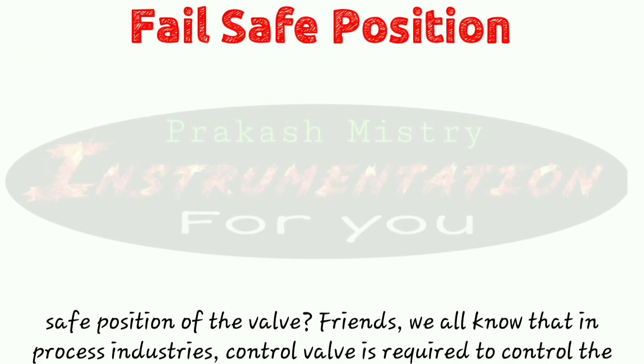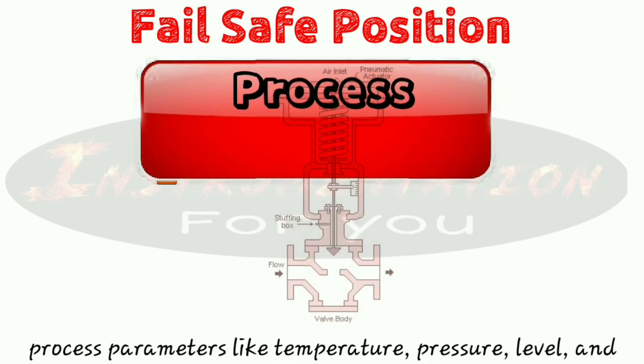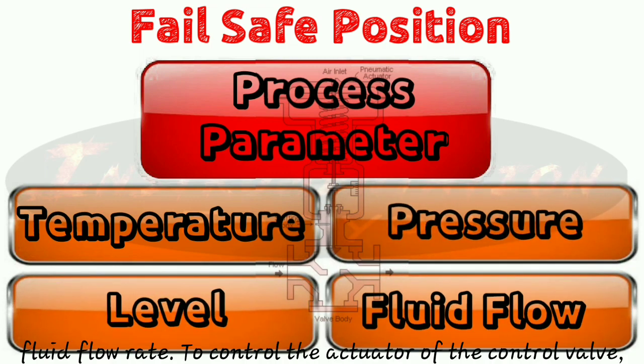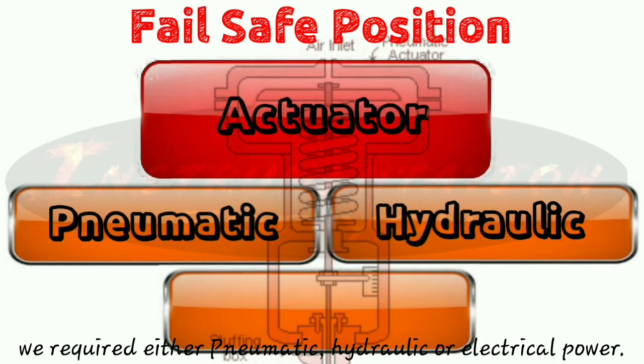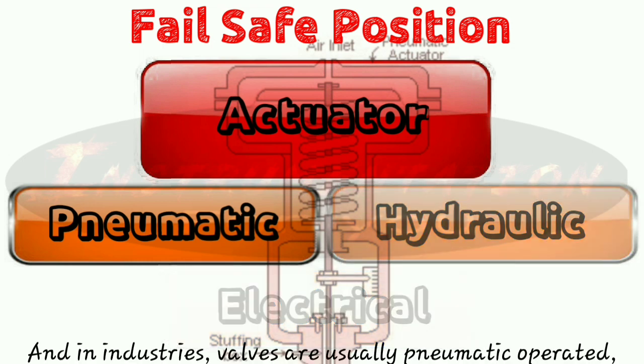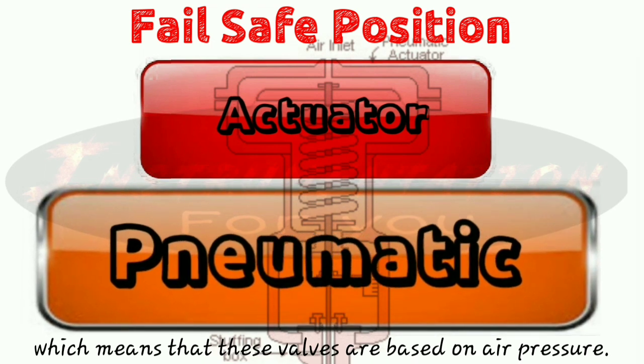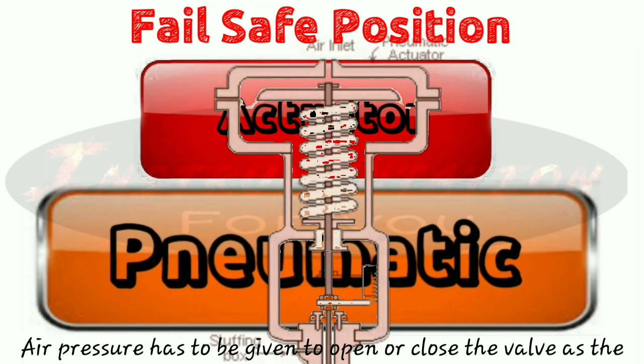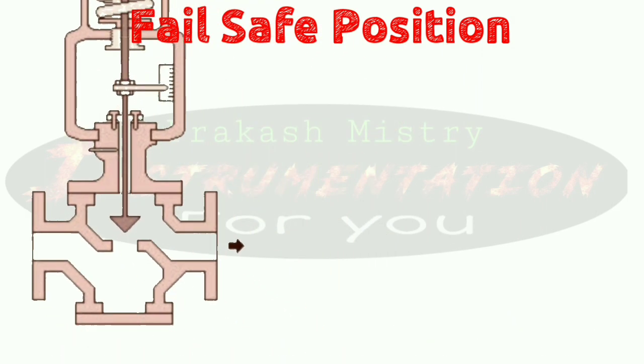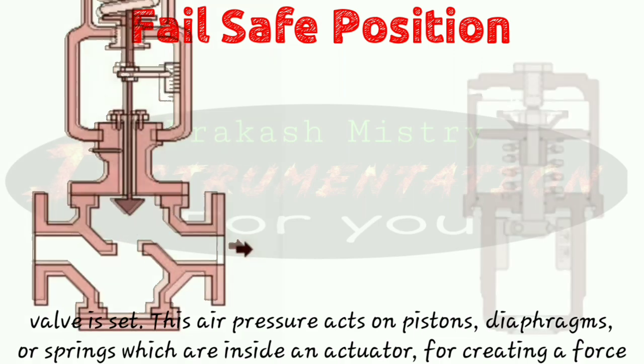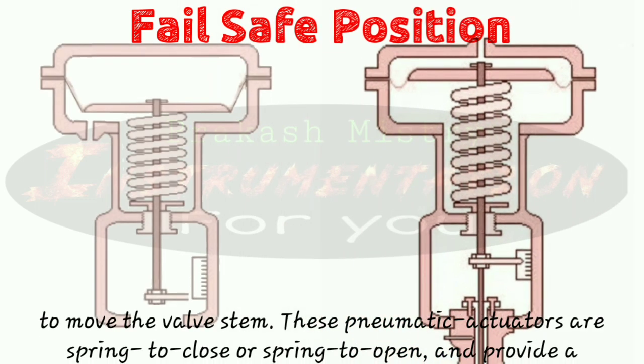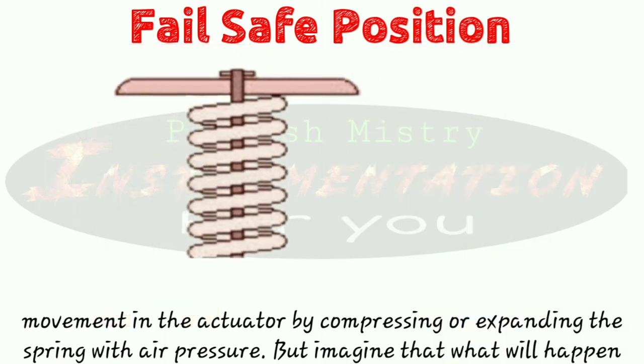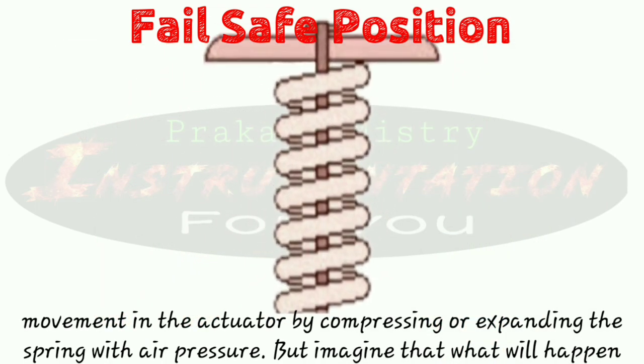We all know that in process industries, a control valve is required to control process parameters like temperature, pressure, level, and fluid flow rate. To control the actuator of the control valve, we require either pneumatic, hydraulic, or electrical power. In industries, valves are usually pneumatically operated, meaning they are based on air pressure. This air pressure acts on a piston, diaphragm, or springs inside the actuator to create a force that moves the valve stem. These pneumatic actuators are spring-to-close or spring-to-open, and provide movement by compressing or expanding the spring with air pressure.